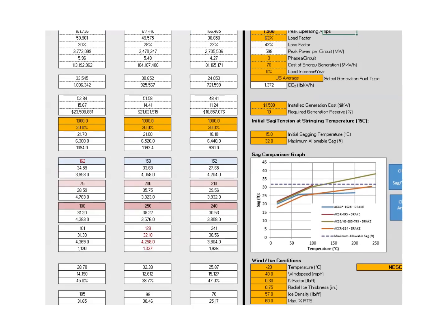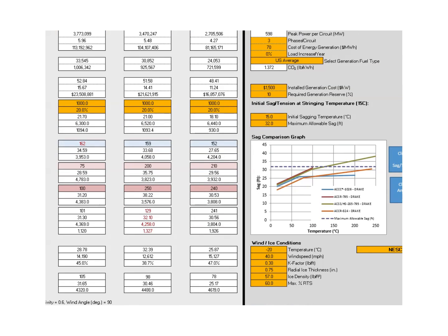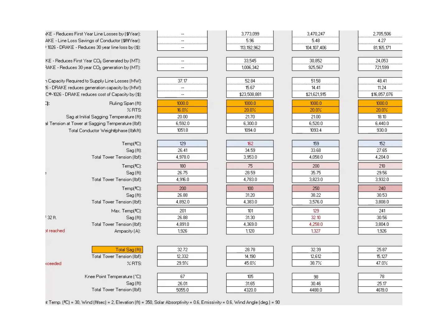We'll scroll down a little bit. You can see that in this scenario, we're assuming an NESC heavy condition, that that can be adjusted. The NESC provides a temperature of minus 20 degrees C, wind speed of 40 miles an hour, K factor of 0.3 pounds per foot, radial ice thickness at 0.75, 3 quarters of an inch, and ice density at 57 pounds per cubic foot. Maximum allowable RTS is 60%. Scrolling over, so we can see differences in the sag under these various conditions. The percent of RTS, ACCC would be about 30% RTS, ACSR about 45% RTS, 3M's product about 47% RTS under extreme high load conditions.